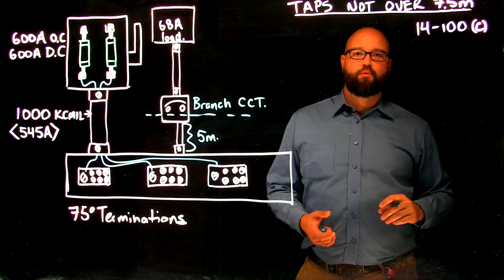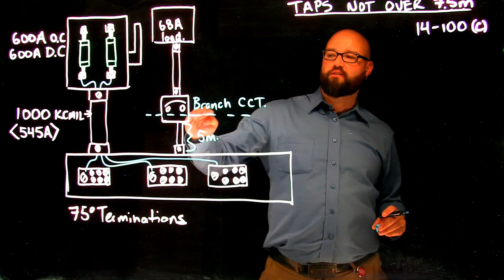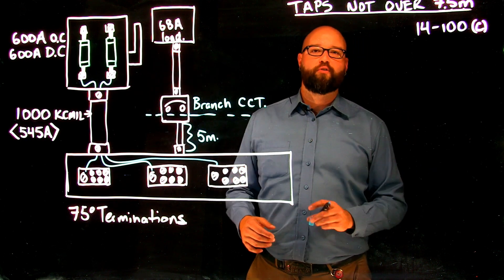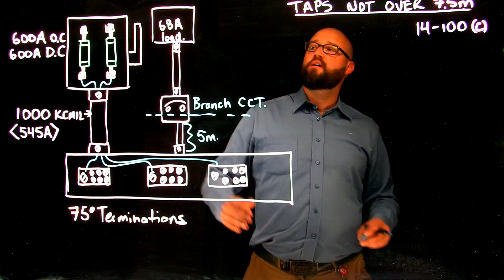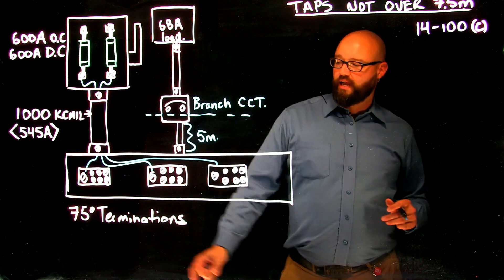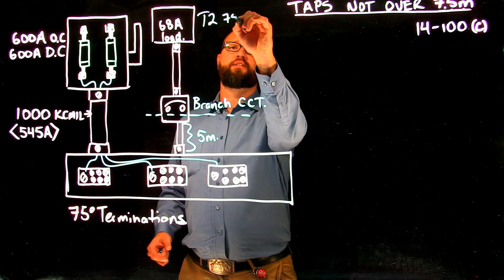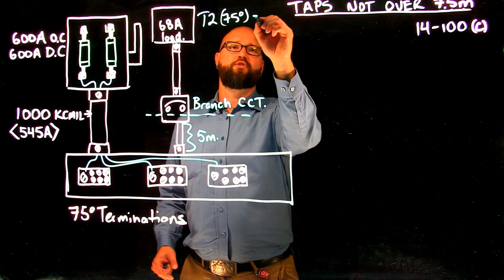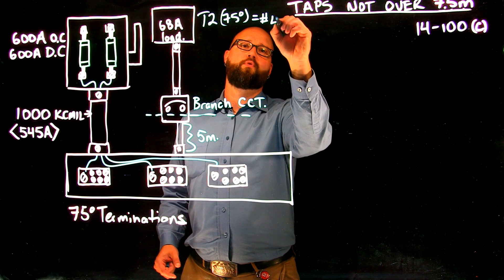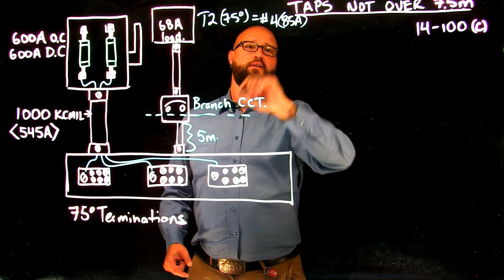I would do this just as I would do any other branch circuit calculation. It's on the downstream side of an overcurrent so there are no special rules as far as tap conductors. I have a 68 amp load. Again with the 75 degree termination I can go table 2 in the 75 degree column and I can choose a number good for 85 amps.